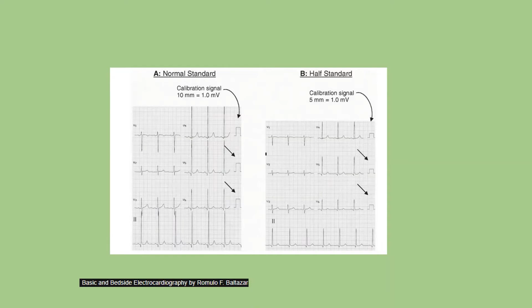Now I can play with the calibration the way I like. I can increase the calibration or I can decrease it. Now this is half standard, where 5 mm equals 1 millivolt. See, this is the same patient. Look at the QRS complex voltage. It decreases a lot just by changing the calibration. So before you think of low voltage and the causes of low voltage, make sure that the standard calibration signal is set right. Okay.